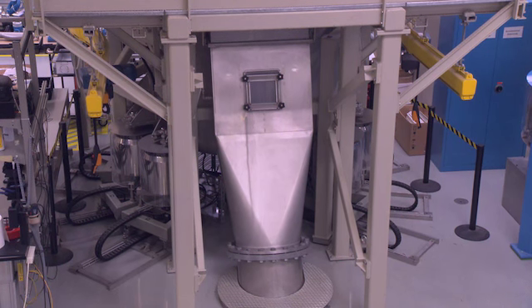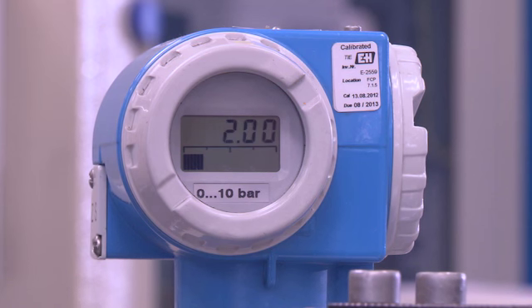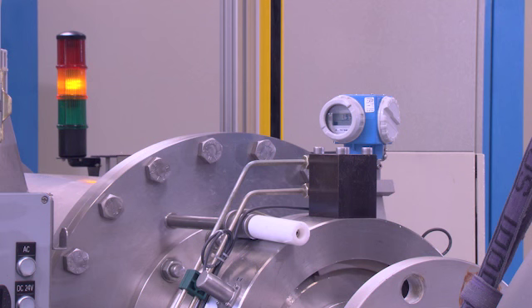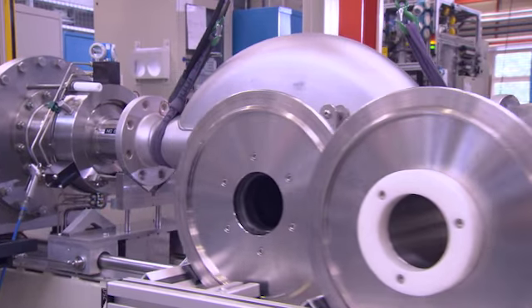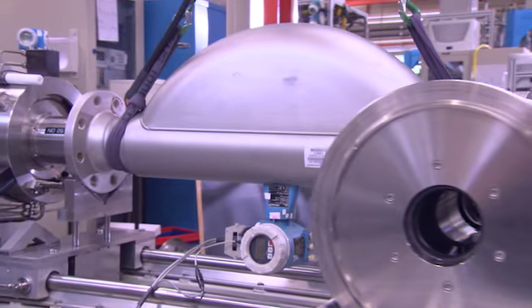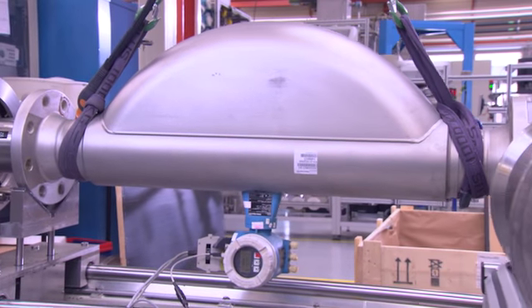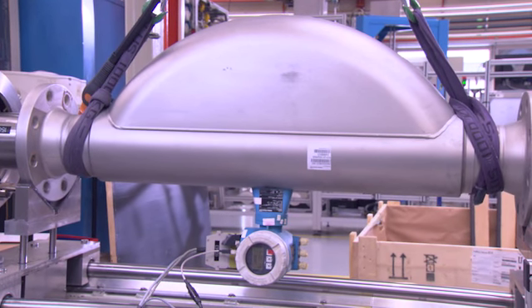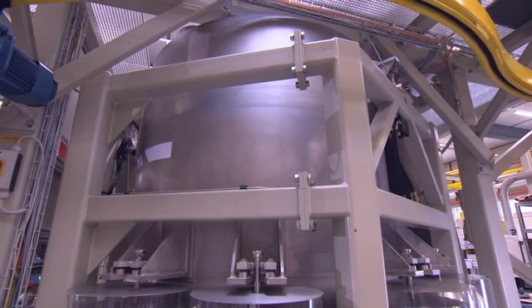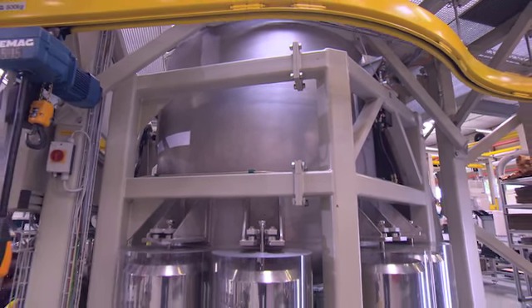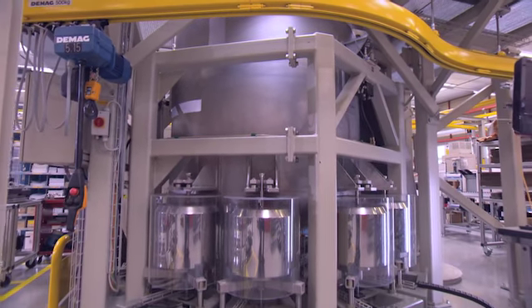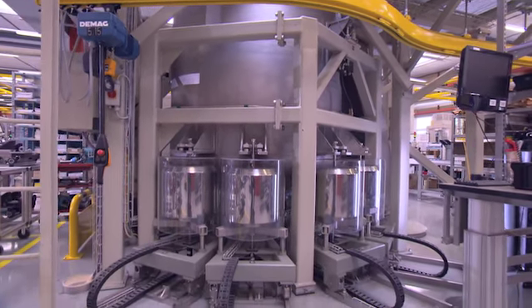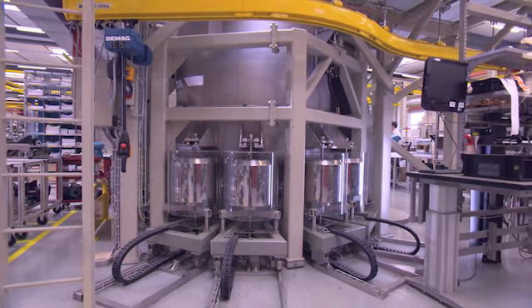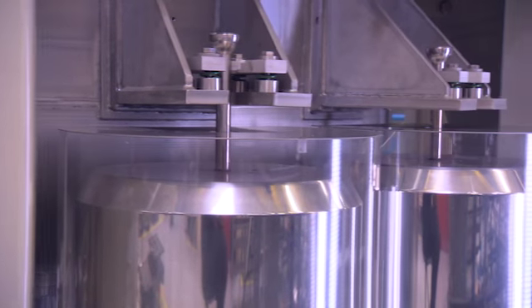The answer is traceability. This means that all testing equipment, for example for weight, pressure, temperature, and time, and therefore the calibration rig itself, can be traced to the national reference standards of a country. This traceability is ensured by an uninterrupted chain of calibrations. The most important test equipment for gravimetric calibration rigs are a scale and its weighing container. These, together with a time measurement, are used to determine the reference flow rate.